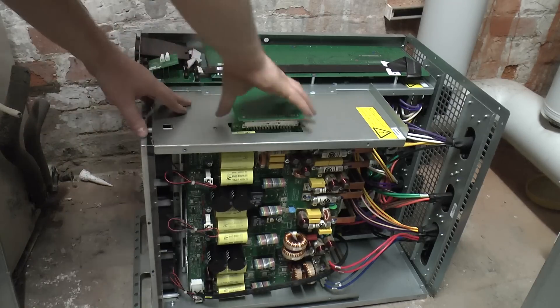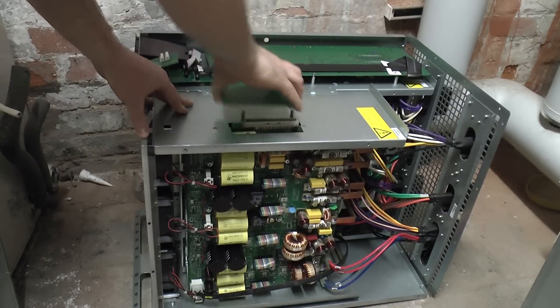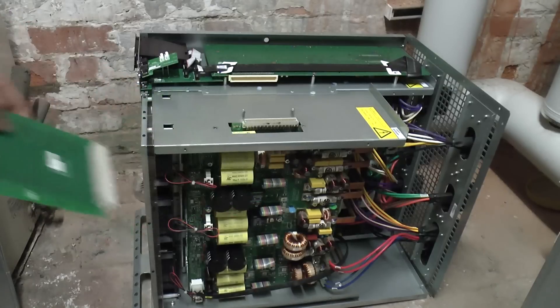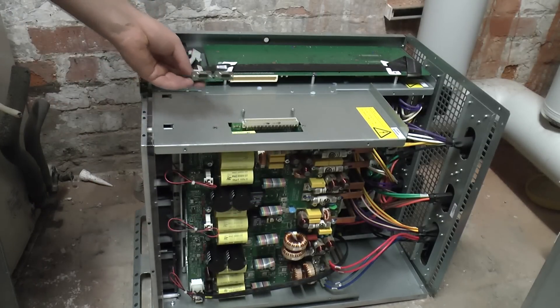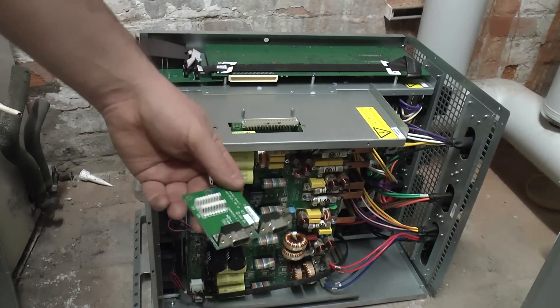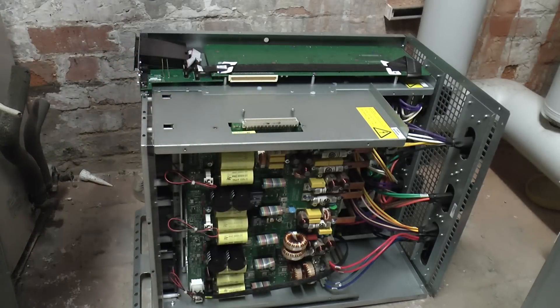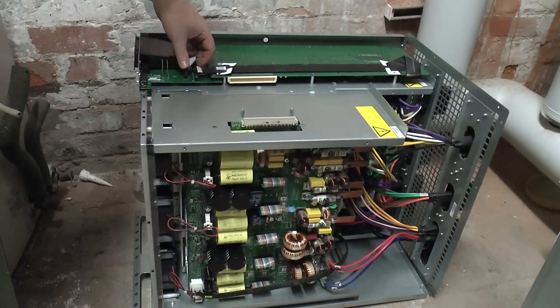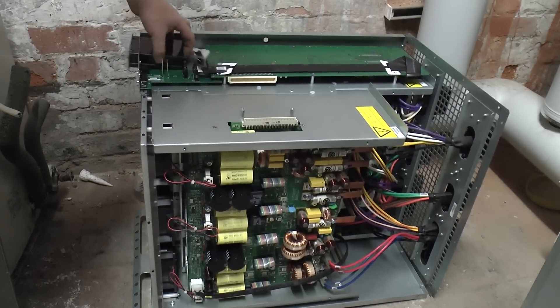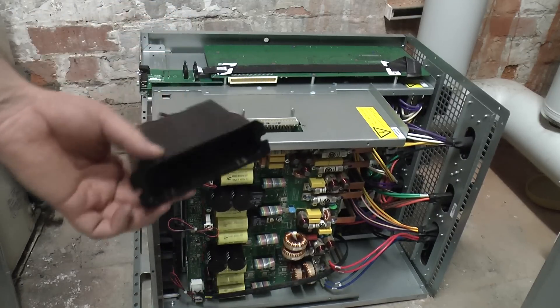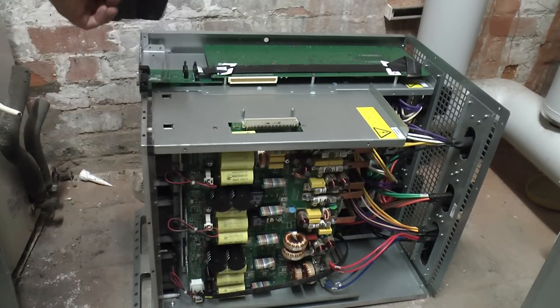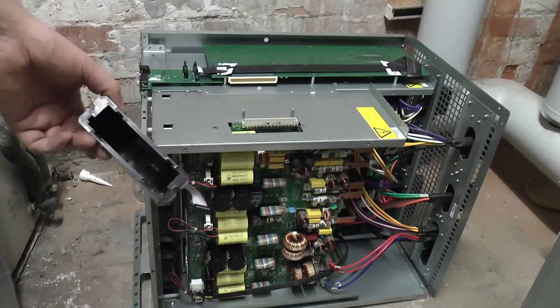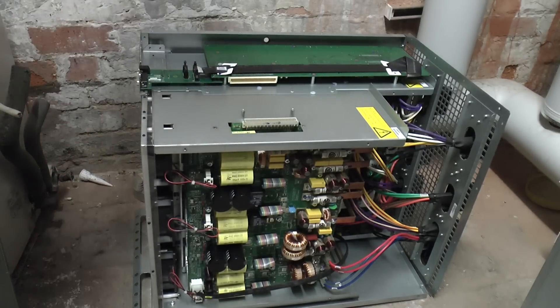You can get a 20kVA version of this UPS with a big blanking plate on this side of the front panel. The 40kVA has the whole thing. So you've got this daughter board here, which just has nothing on it at all. That's a serial interface panel. Again, no components on there. This is where the accessory slot is for the front. You can put your network management cards in or multi-port serial cards, environment monitors, whatever.